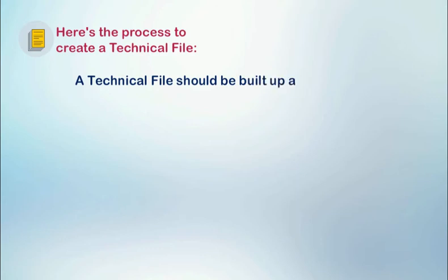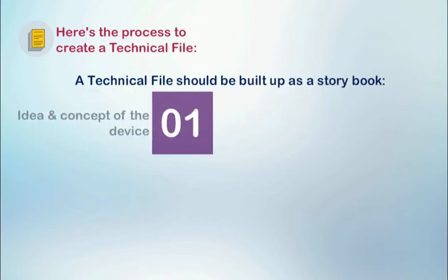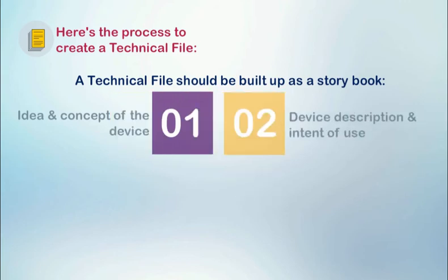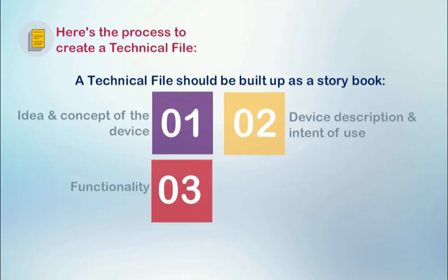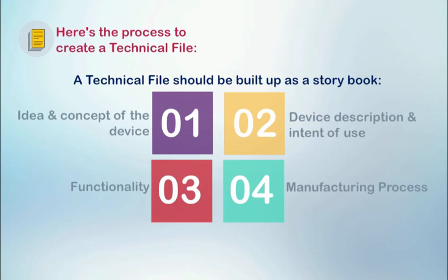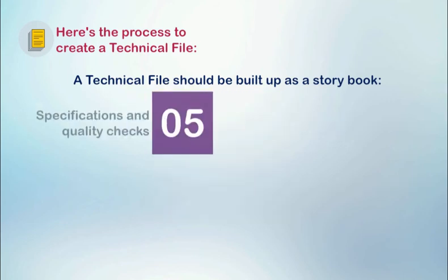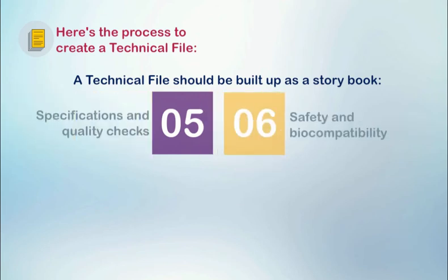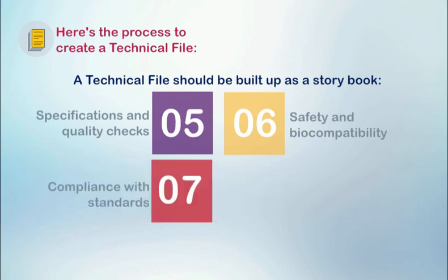Here's the process to create a technical file. A technical file should be built up as a storybook. You will need to start with the idea and concept of the device. Describe what the device does and the conditions it treats. Describe the device and how it works. Describe how it is manufactured, including microbiological aspects and sterilization. Describe the specifications and quality checks. Describe the aspects of safety and biocompatibility. Describe how it complies with standards, and more.